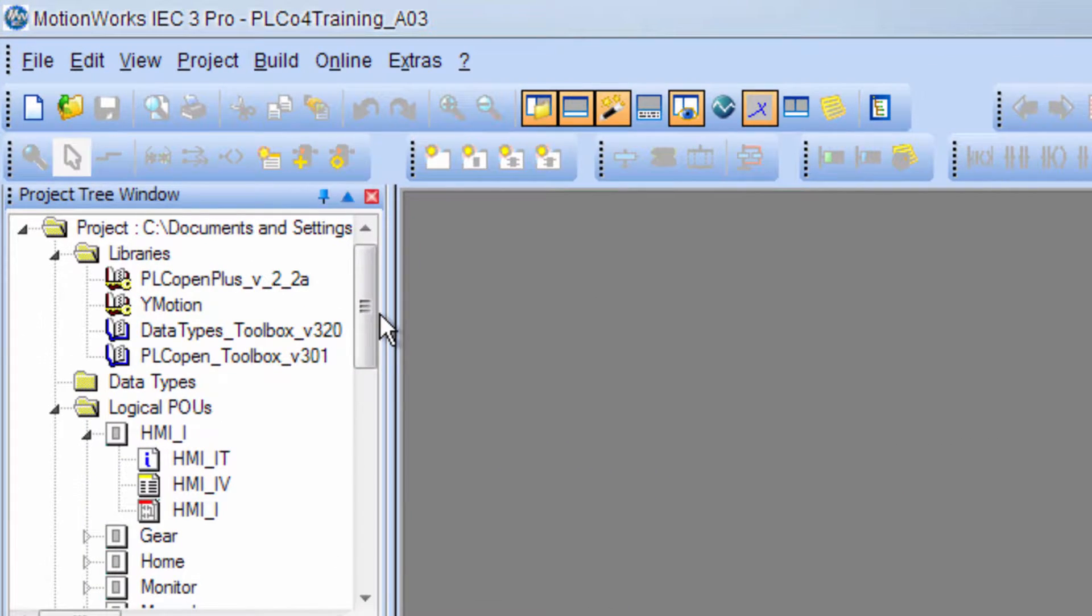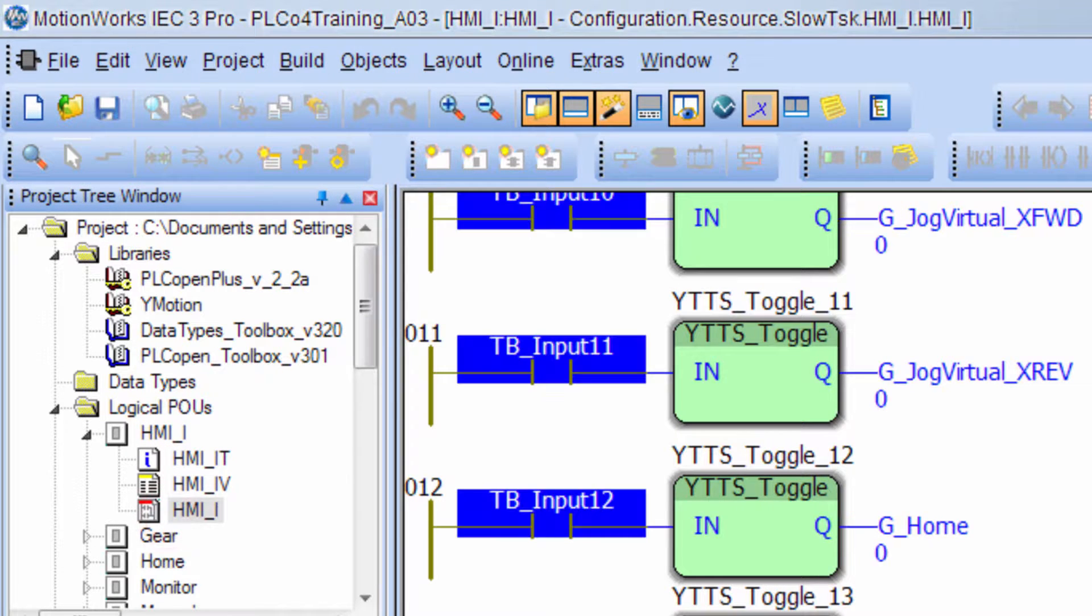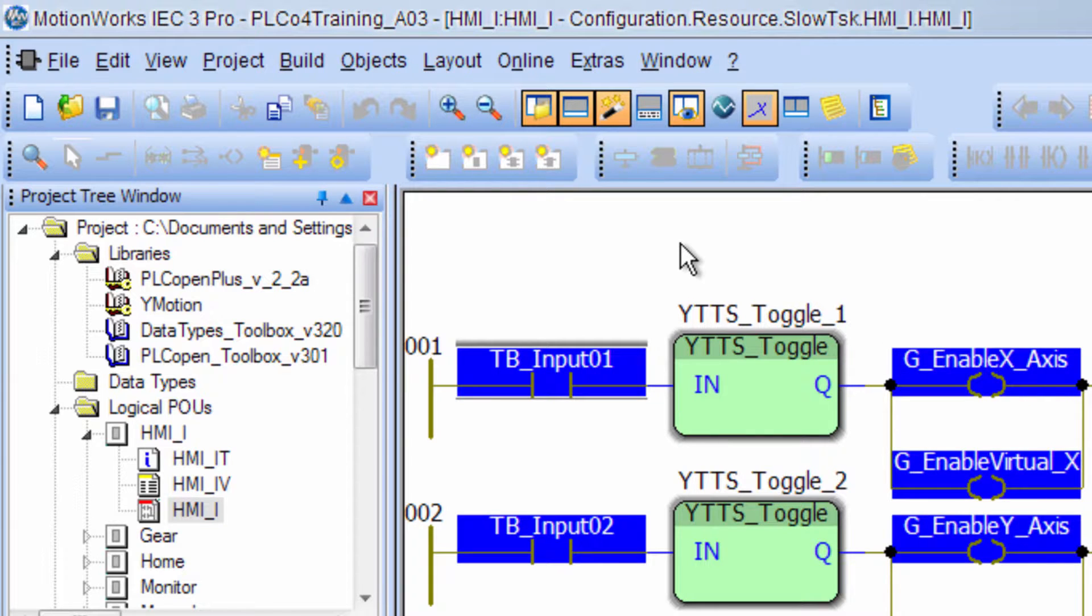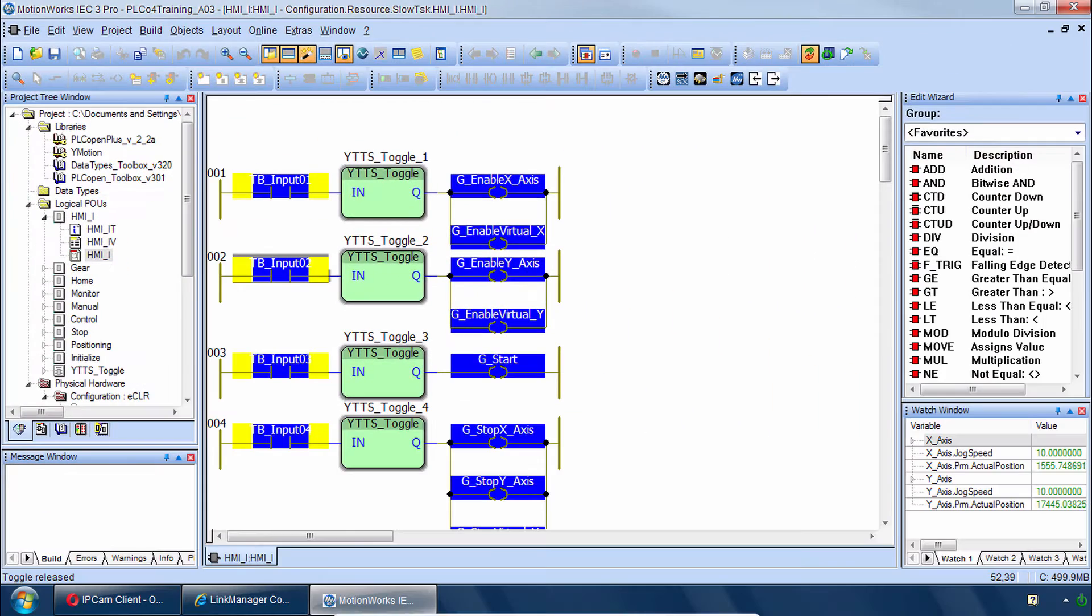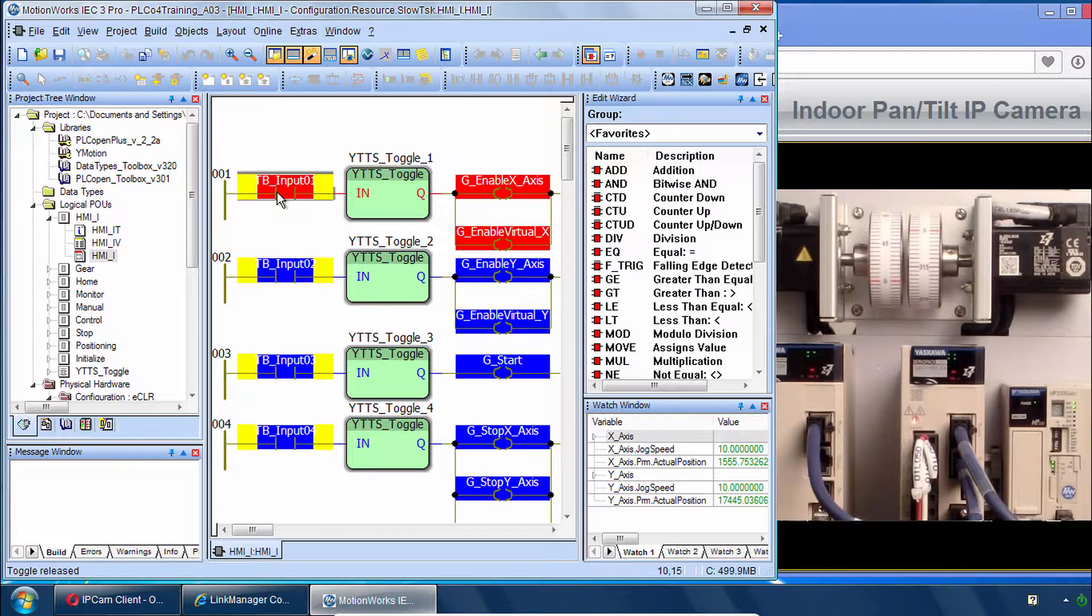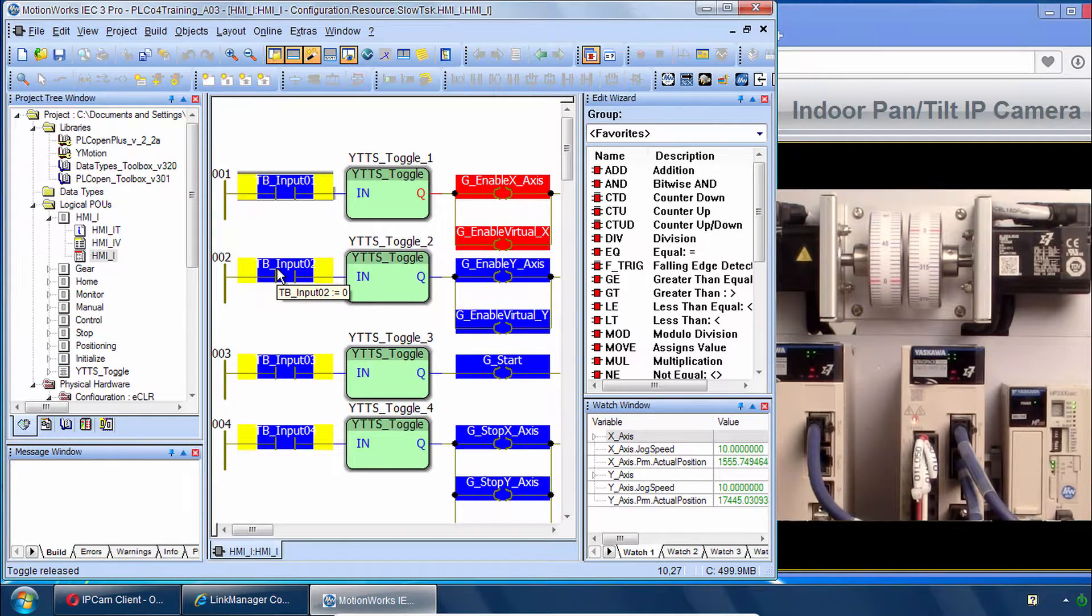Go to Debug Mode. Close these variables. And the POU you'll use the most here is the HMII POU. Scroll to the top there. This is where you can enable the X and Y axis. And the easiest way to do that is to go to the Online menu and choose Toggle Boolean Values. Now I'll adjust my window so I can see the demo off to the side. And click to turn on Servos X. That's confirmed by the Amplifier Front Panel Display. And Y.